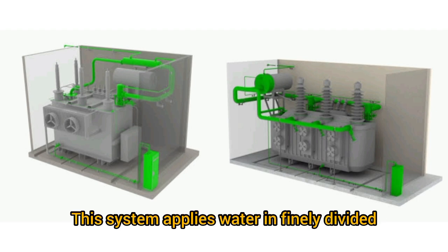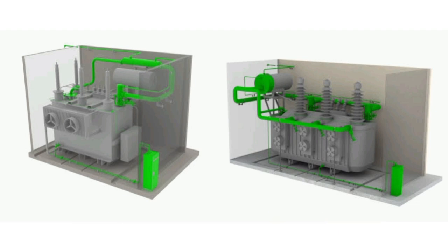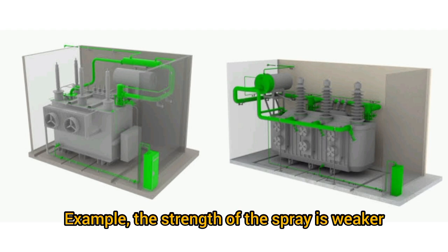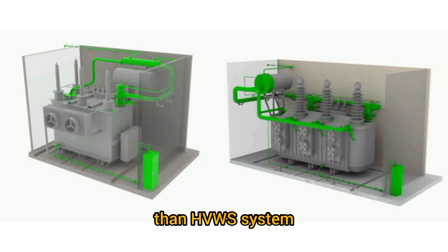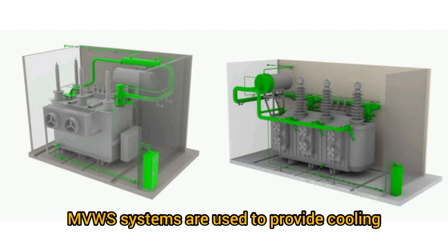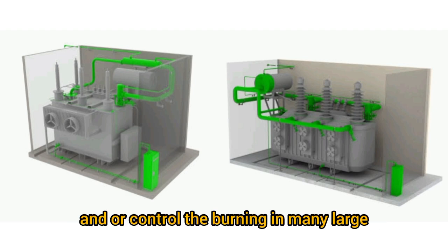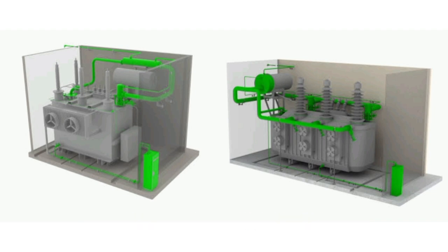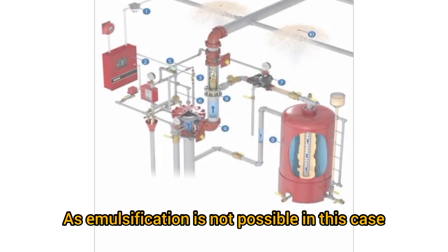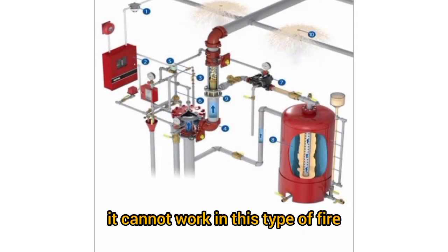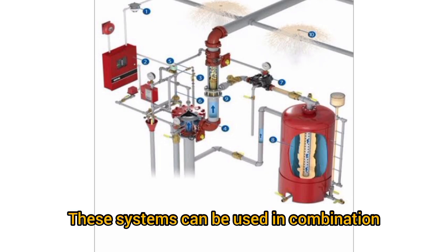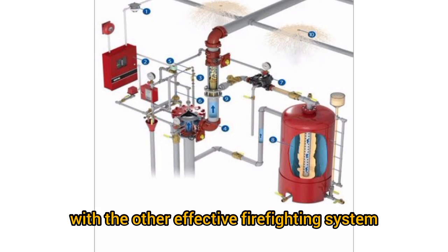This system applies water in finely divided droplets at medium velocity. Example: the strength of the spray is weaker than the HVWS system. MVWS systems are used to provide cooling and/or control the burning in many large-scale industrial applications. As emulsification is not possible in this case, it cannot work in this type of fire. These systems can be used in combination with other effective firefighting systems.